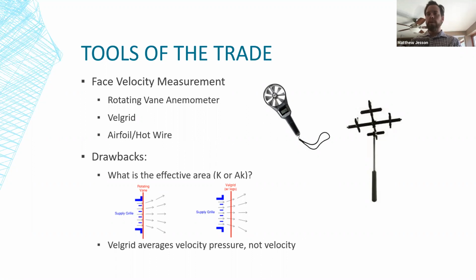So it comes with these 1.5 inch legs or standoffs that hold it off of the surface 1.5 inches. So on this supply grill, you can see the plane that you're taking that reading in is after the air comes out of the grill and starts to spread out a little bit. That becomes really difficult to evaluate. What is your effective area? What's the area of that airstream then? And it'll change depending on the type of outlet.